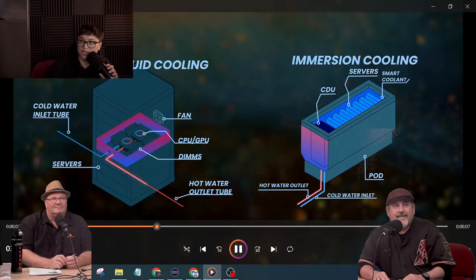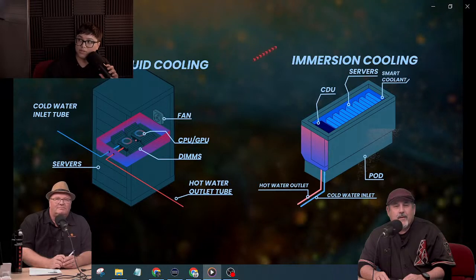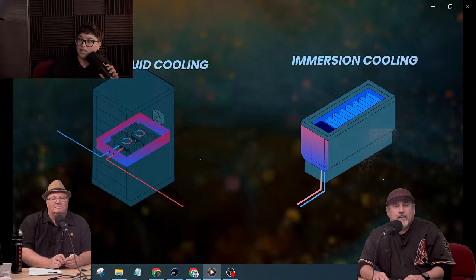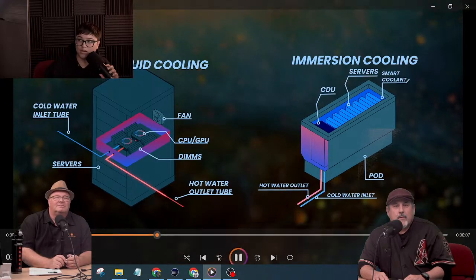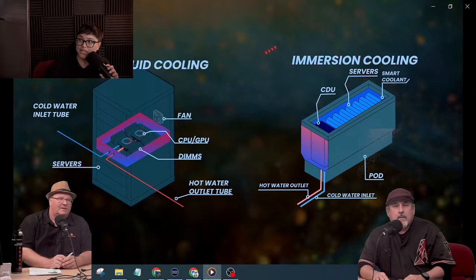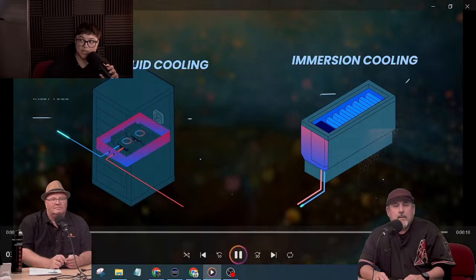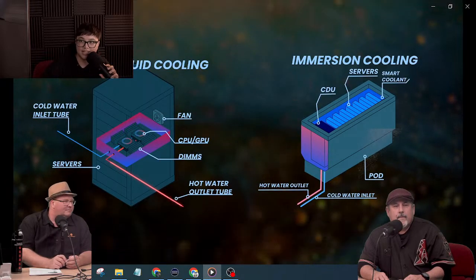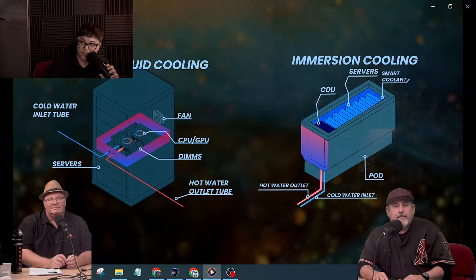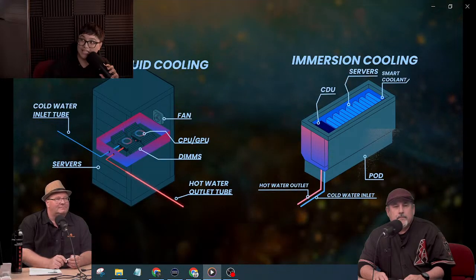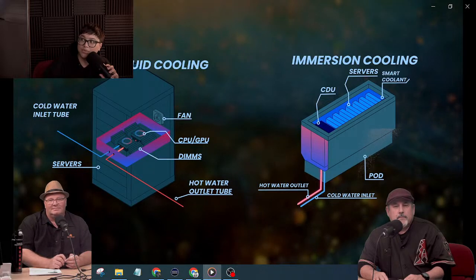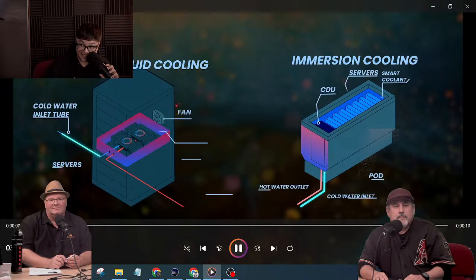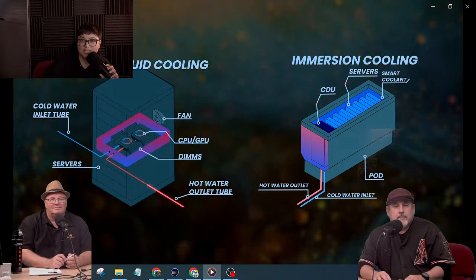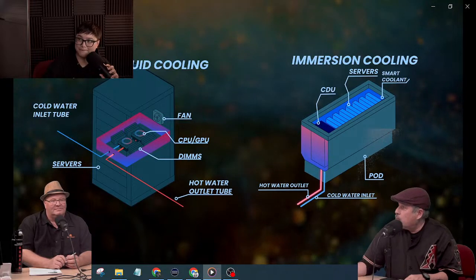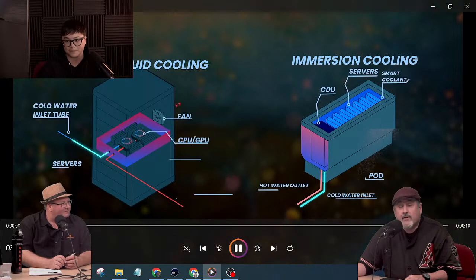For sure. Direct-to-chip, or DLC, you have cold plates attached directly to the processors. A coolant, often mixed with water and additives, flows through the plates, absorbing heat before it's taken away to be cooled in a heat exchanger. Immersion is completely different. The entire servers or components are submerged in non-conductive fluid, like dielectric oil. Heat is absorbed by the fluid and carried away, often with significantly less power needed for fans because you don't really need them.